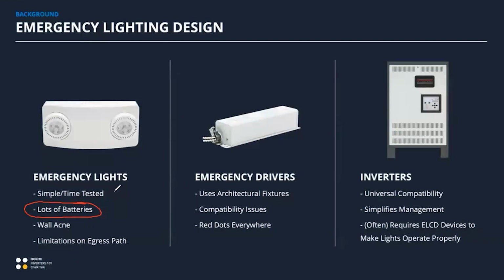Once a year, you have to do a full duration test to prove the batteries still have enough capacity to illuminate the space for the required 90 minutes.